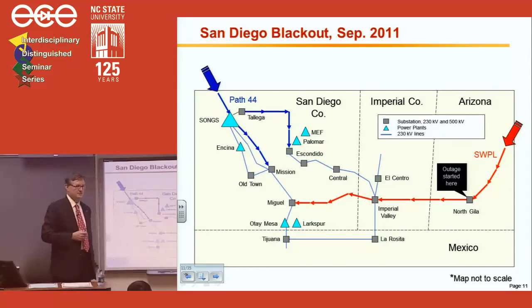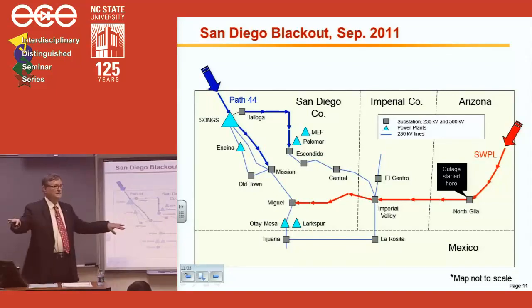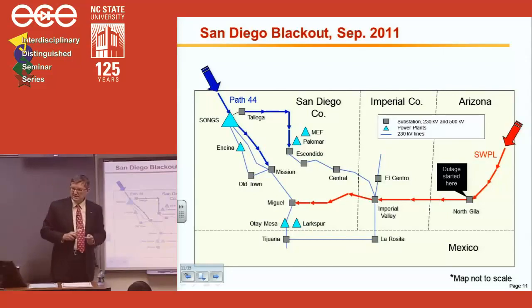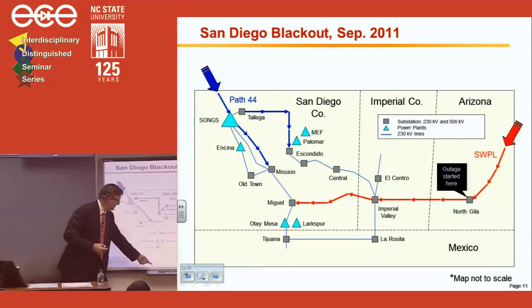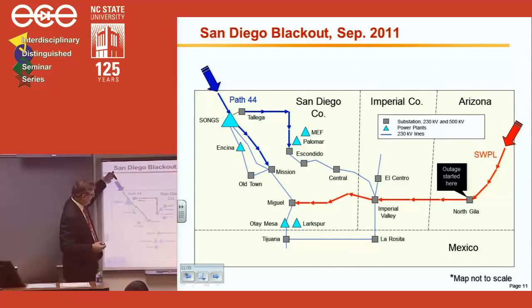Generation in Mexico tripped, and it was unrelated—it had nothing to do with that series capacitor being tripped. But that's what happens in life. They disconnected this generation, and as soon as there's no generation coming here, suddenly you load this path, so-called path 44.